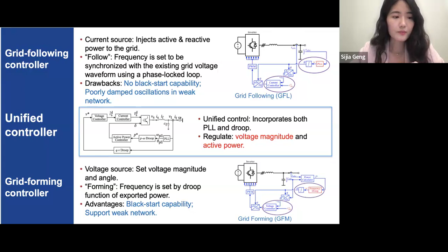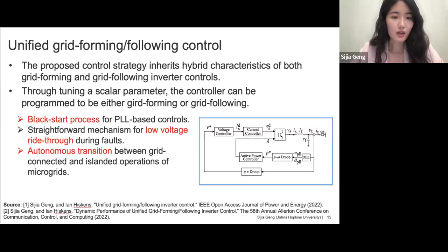We use this unified controller as a tool to understand the interactions of grid-forming and grid-following and their impacts on the grid dynamics at different locations in a systematic way, because now, through the tuning of a single parameter, the droop constant in this unified control, the controller can be tuned to fall towards either grid-forming or grid-following. We did a variety of case studies using several benchmark power systems, and the control scheme appears to be very robust. We also discussed in these two papers the black start process for this PLL-based control, as well as a mechanism for low voltage ride-through, and most importantly, it can achieve autonomous transition between grid-connected and islanded operation of microgrids.